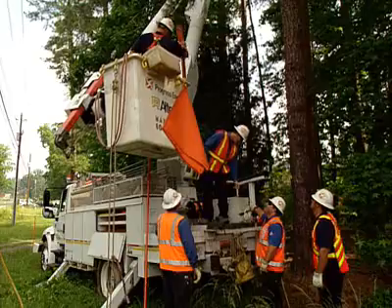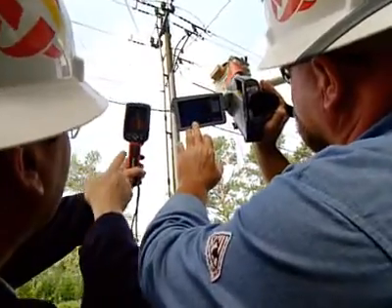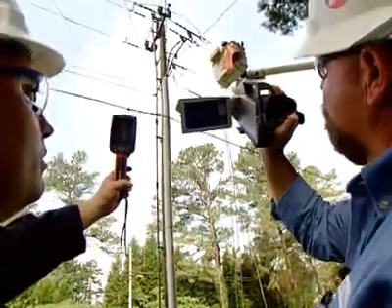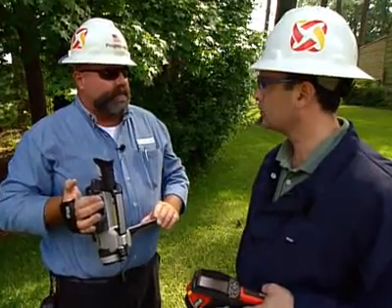We can detect problems before they fail or while someone is up there making repairs. We found some linemen that are actually doing some repairs. We took the 640 and looked at the opportunity — in turn, it made it safer for him and myself. You don't have to climb a transmission tower to do an inspection. You can do it from the ground, which saves time and money. We can find a problem, have it corrected, and go back and re-scan to know that we'll have continuity back. We'll come back and re-scan after everything's put back to normal and make sure the job is done.